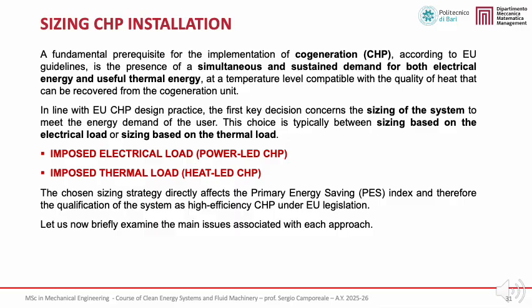In practice, this choice is between sizing the CHP unit based on the electrical load or sizing it based on the thermal load. These two approaches are commonly referred to as power-led CHP, or imposed electrical load, and heat-led CHP, or imposed thermal load. The selected sizing strategy has a direct impact on the primary energy saving index, and therefore on whether the system can be classified as high-efficiency CHP under EU legislation. In the next slide, we will examine these two configurations in more detail.